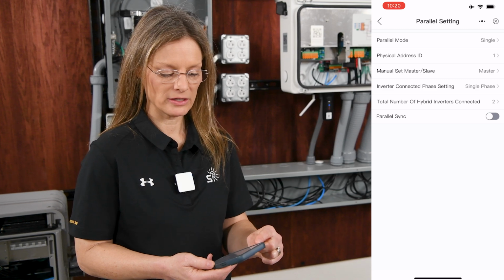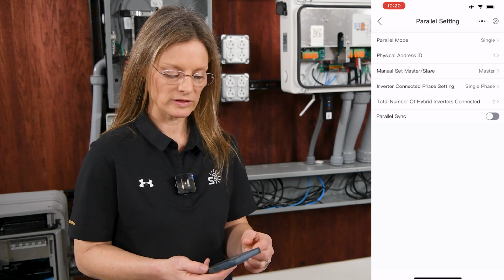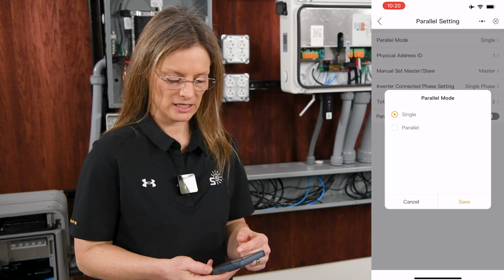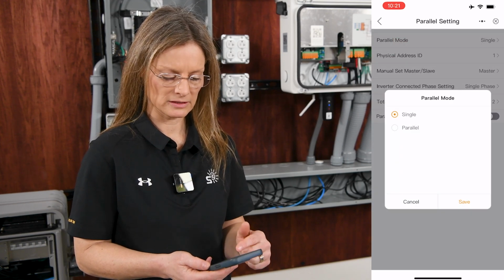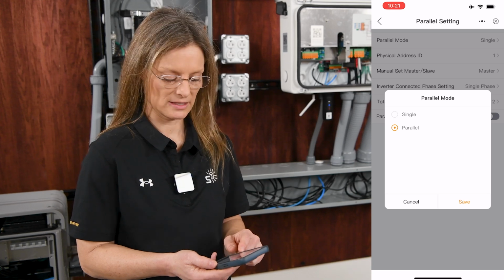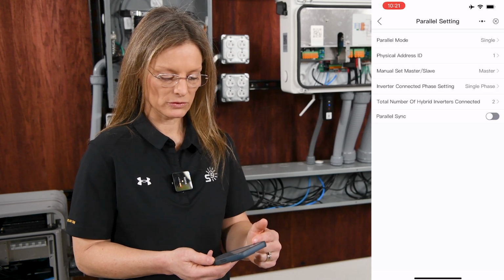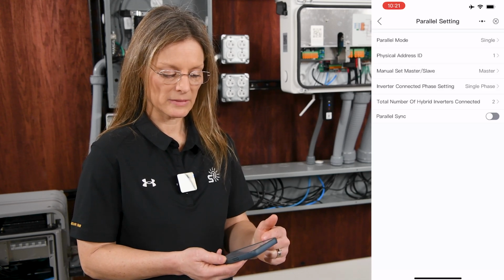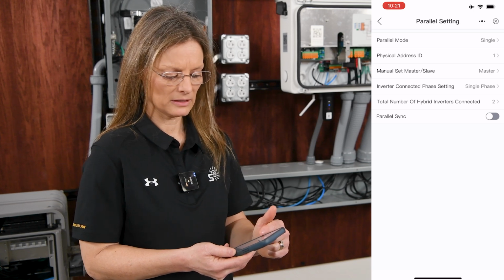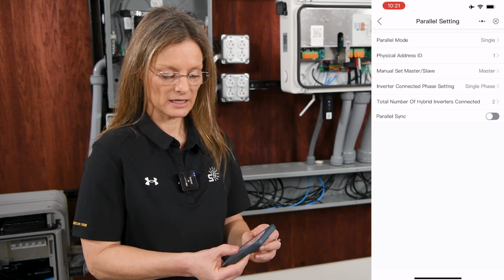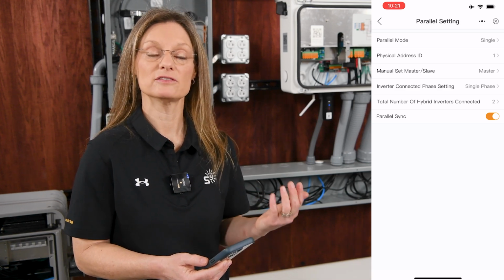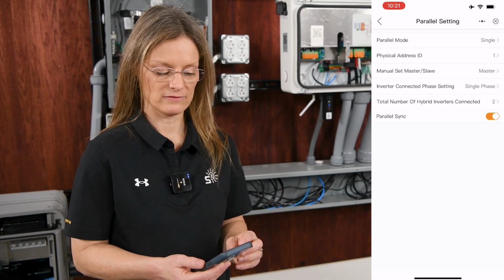Notice the parallel mode here, it says single. I only have one inverter, but if you were connecting more than one, you would select this and say parallel. So if you selected parallel, at this point you would say save. Now, even though this one is my master, at the very bottom where it says parallel sync, I would want to select that on all of my inverters, even on the master, to make sure that all of the settings that I have set on my master and my batteries would be saved throughout all of my inverters.